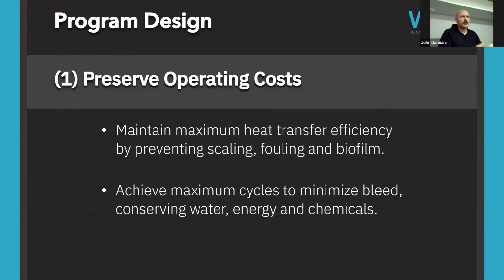So number 1, for preserving operating costs, well, we want to maintain our heat transfer efficiency by preventing the scale, fouling, and any sort of biofilm, right? So that'll maintain our heat transfer efficiency. That addresses the operating costs. We also want to achieve maximum cycles. That's going to minimize bleed from the system, which is going to conserve water, conserve energy, and chemicals. Okay, so that's how we address that first objective.